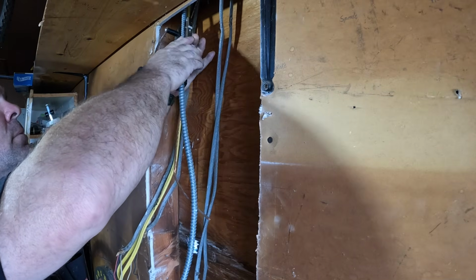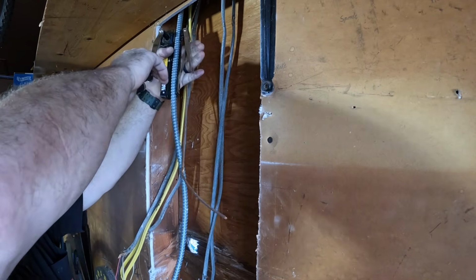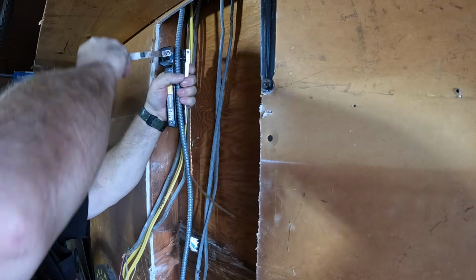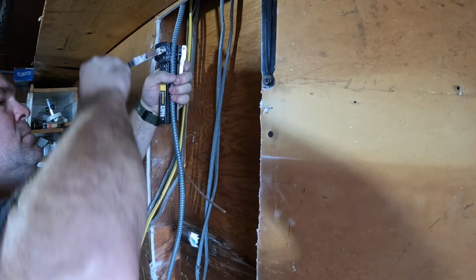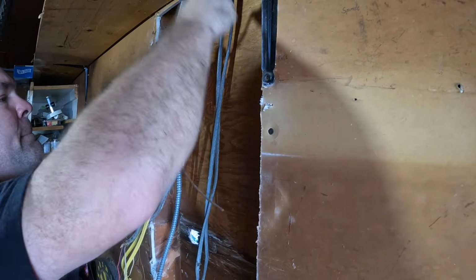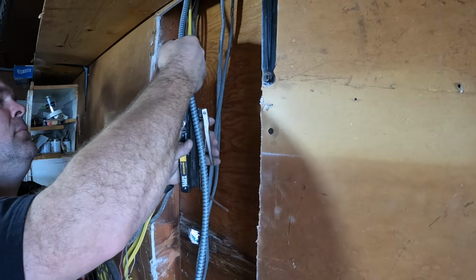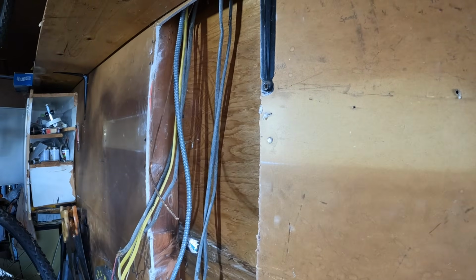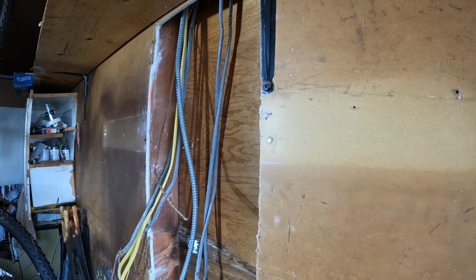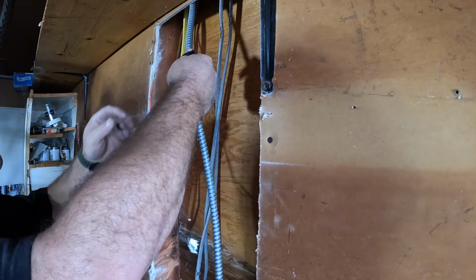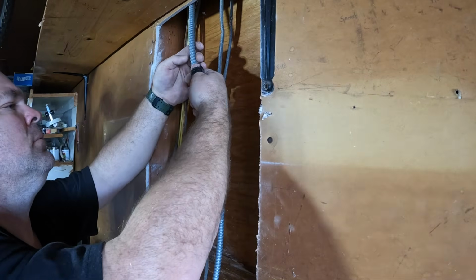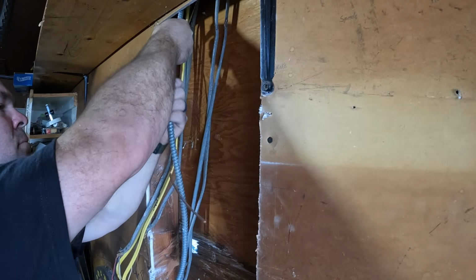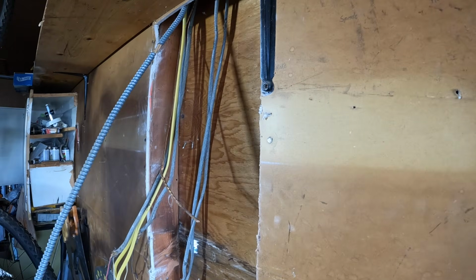Now here, the only circuit that we had with armored cable, this is actually a 20 amp circuit for the dryer line. I believe this is a 3-wire here, but it's only 20 amps. And then normally a 5,000 watt electric dryer is a little bit more than 20 amps, and you should have run 10-3 gauge wire. It's working, and so we left it like that.